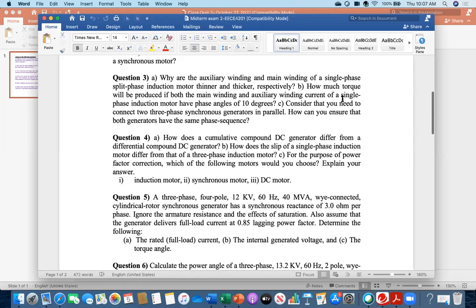Part b: how much torque will be produced if both the main winding and auxiliary winding current of a single-phase induction motor have phase angles of 10 degrees? Zero — because torque is proportional to I_a × I_m × sin(alpha), where alpha is the angle difference between the two currents. If both have the same phase angle of 10 degrees, alpha is zero, and consequently the torque is zero.